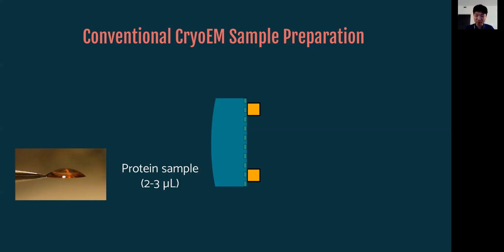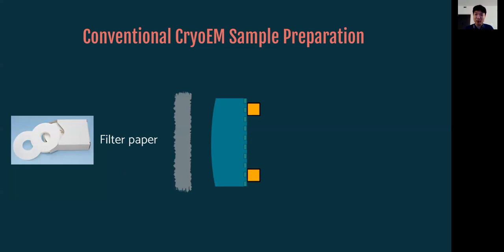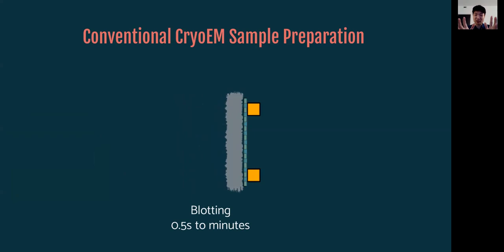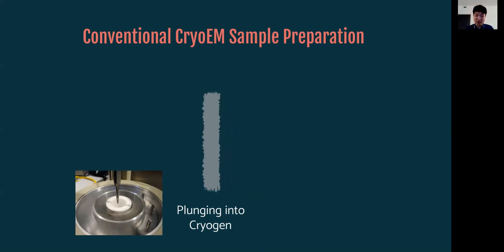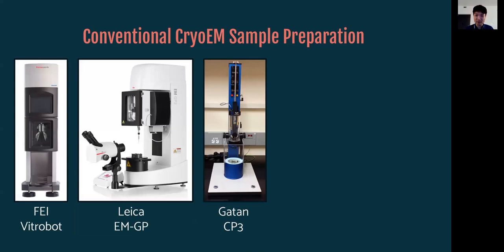And this is conventionally done using filter paper. So we actually push a filter paper against the grid. And this process called blotting actually occurs and the excess liquid is wicked away. And you're left with a very thin film of liquid present between the holes inside the grid. And this takes around 0.5 seconds to minutes. And once that is done, you pull away the filter paper. You plunge the whole grid into liquid cryogen and freeze it. And then your grid is now ready to go and be imaged in the microscope.